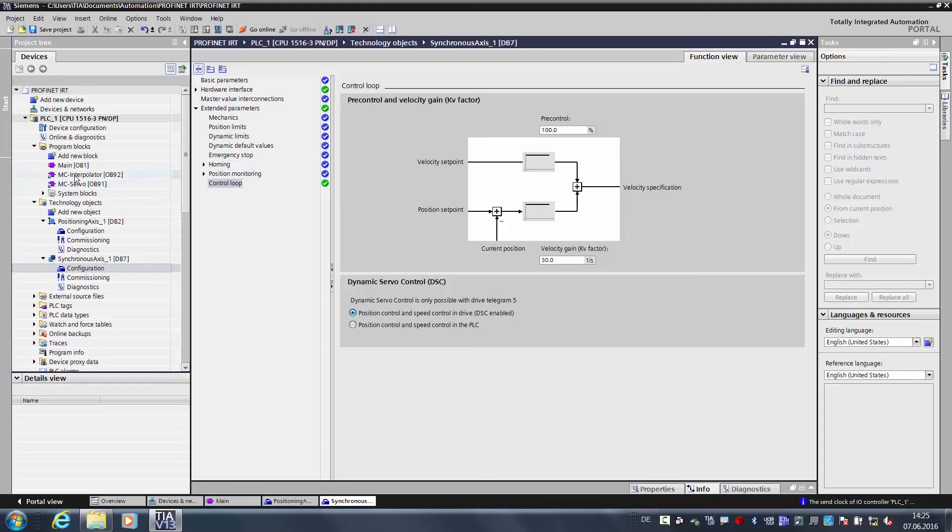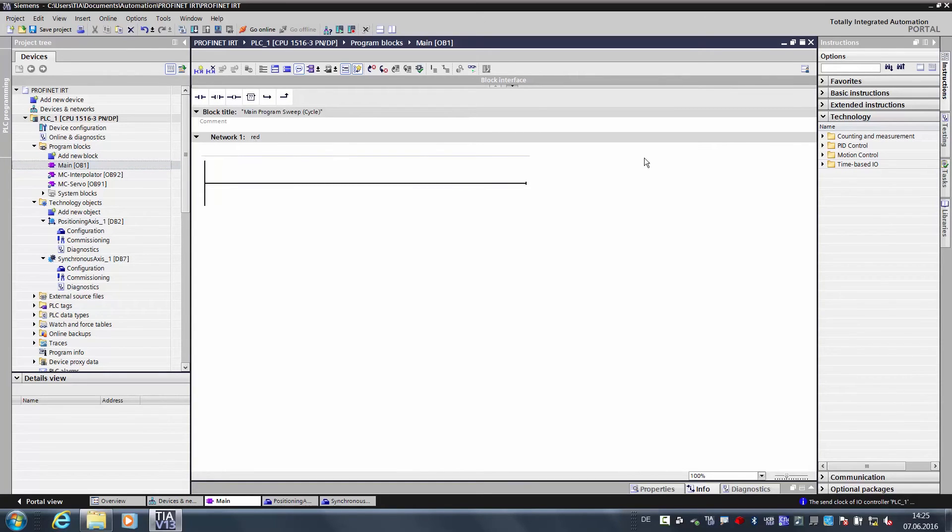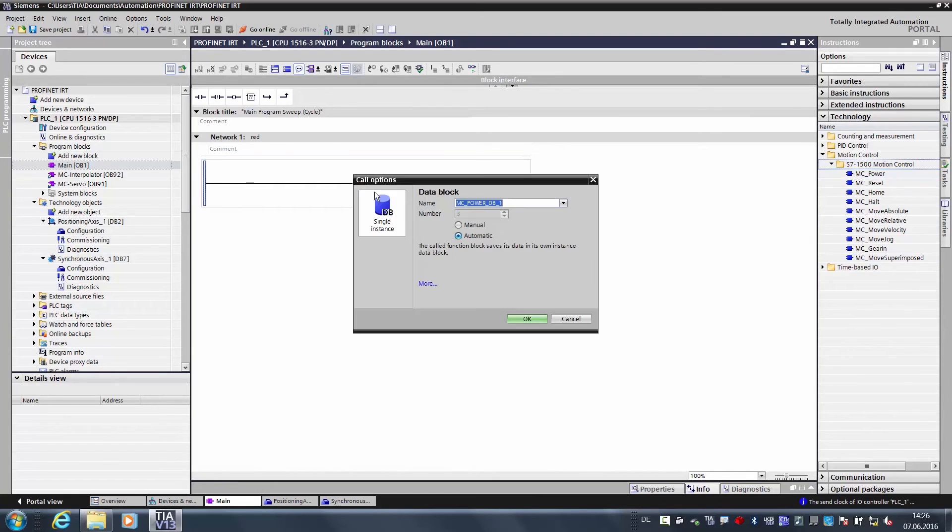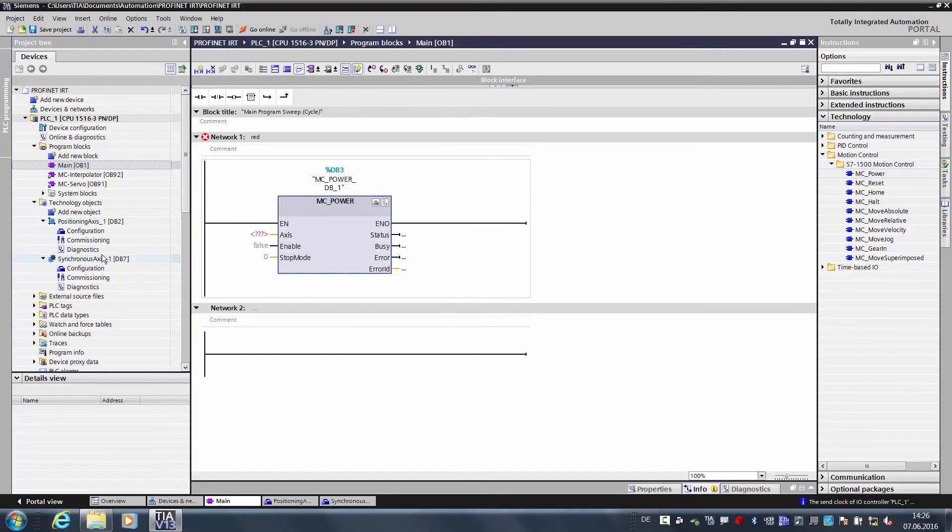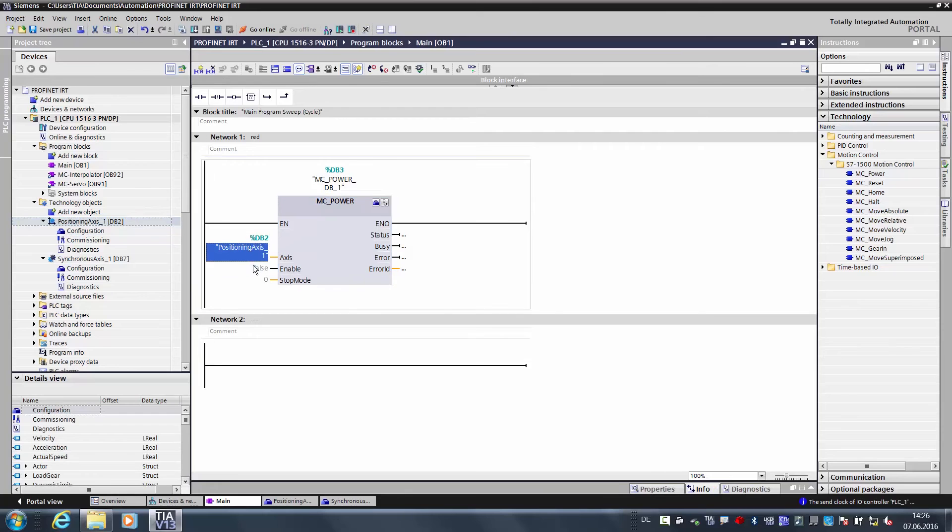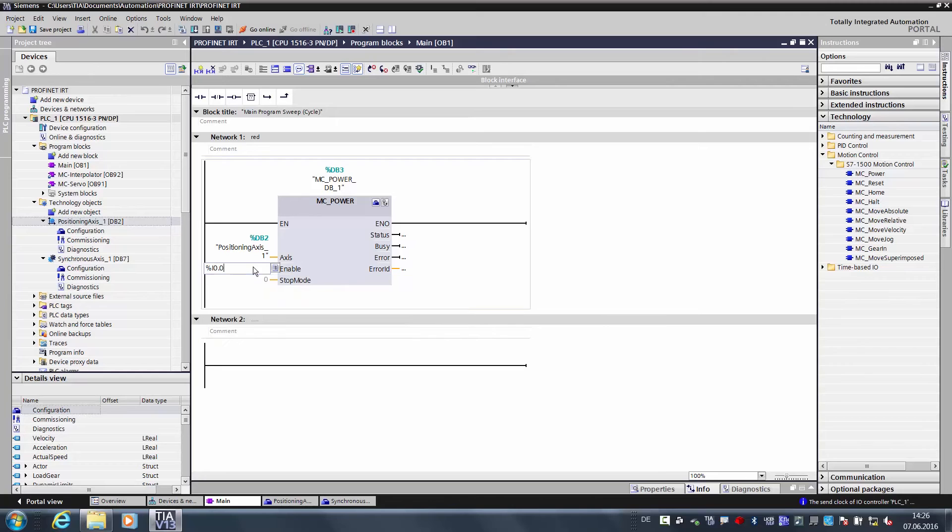Now we want to create a small program for controlling the drives. To do so, we open the main OB1. In the first network, we want to actuate the red axis. Here on the far right, there are various instructions. Here we want to switch on the motion control technology instructions, and with the MC power we will switch on the first axis. Here we still need to assign the axes. The first axis is the positioning axis, and we want to start the axis with the input 0.0.